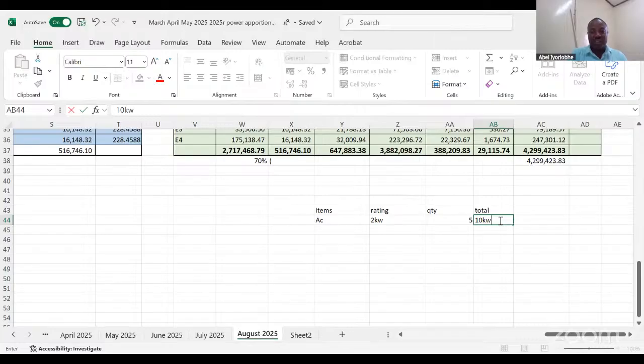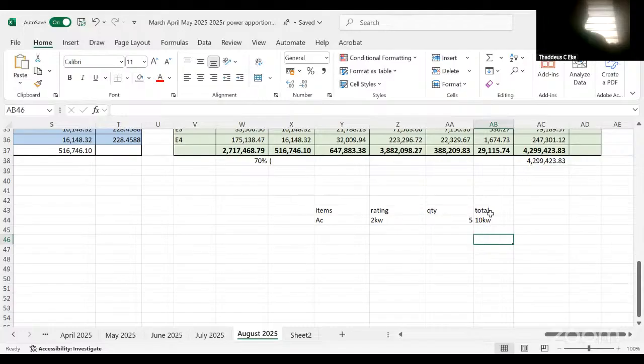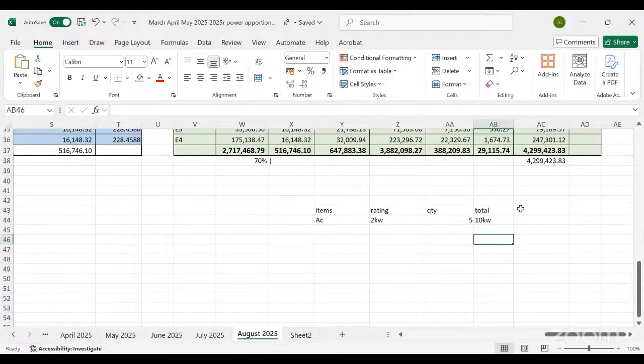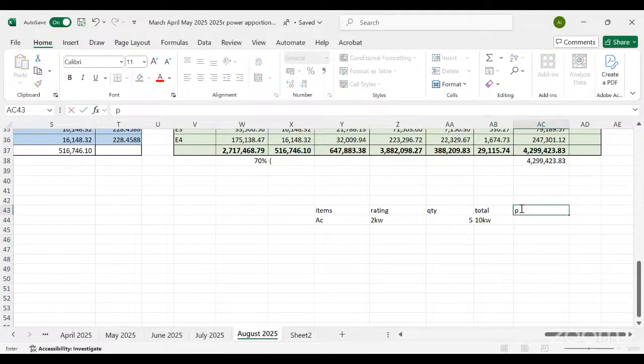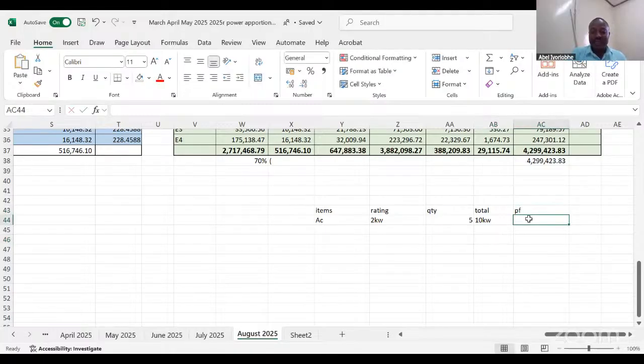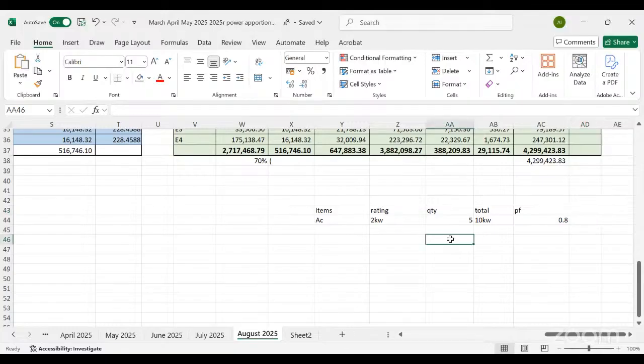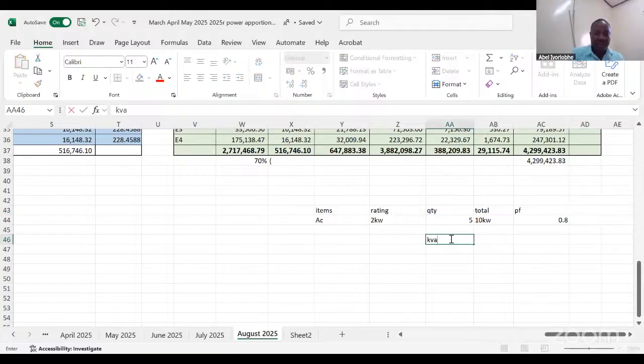I need your participation, right? Yes, we are with you, sir. Total load is 10 kilowatts, and you have a power factor, which is 0.8. This is the industry standard. I'm not the one that did it. Everybody came together to agree on this factor. It's called power factor. It's a multiplying factor. So this is in kilowatts. Your generator, how is it rated? Is it in kVA or kilowatts? kVA.